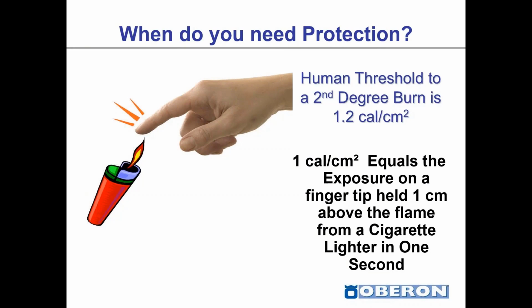When do you need protection? The human threshold for a second-degree skin burn injury is approximately 1.2 calories, based on the Stoll curve. So if you take a cigarette lighter, using the image on the screen here, it's about 1 calorie if you hold that about 1 inch away from your fingertip for 1 second.